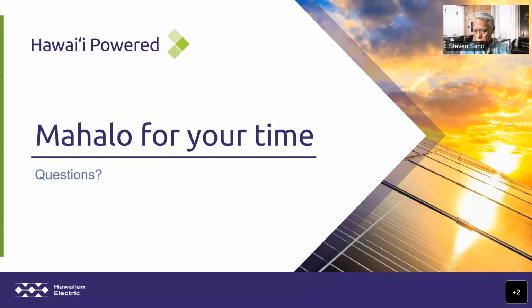Okay. There's a related question that I'll throw in there, just since you mentioned that the grid forming inverters have better behavior, better characteristics than the grid following. Is there any move in HECO towards specifying grid forming in the future for your inverter-based resources, or is that a step that you haven't really contemplated yet? No, we are requiring grid forming inverters for all our future procurements for system resources on transmission and to a certain extent on distribution as well, I believe. So there are a lot of benefits for grid forming inverters. Our current thinking is that they will address a lot of the problems we're seeing. So it's actively in the procurement process. We are specifying grid forming inverters.